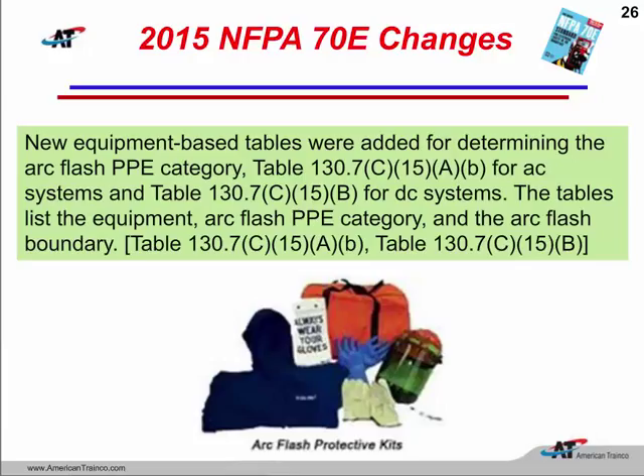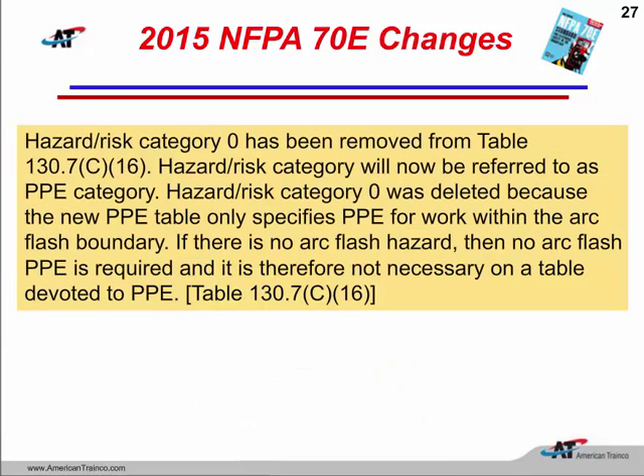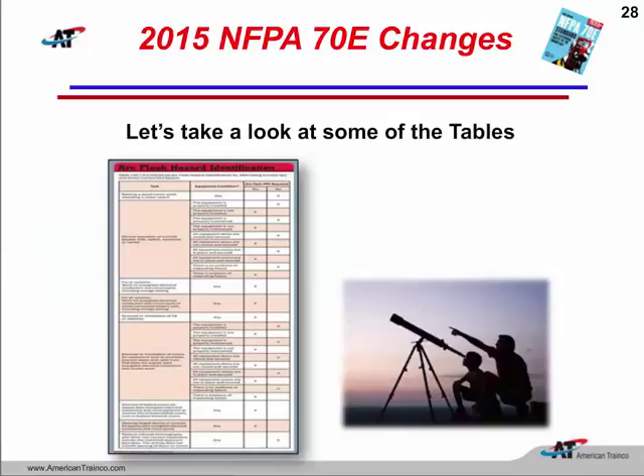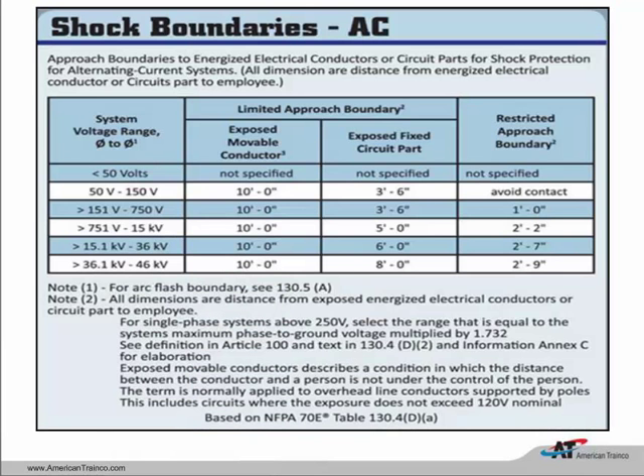So if you walk up to a piece of equipment and you have no label on that equipment whatsoever, these tables are going to be extremely important on how to protect that qualified worker when he approaches that piece of equipment. So they did remove hazard risk Category 0. We have stated that because really there is no arc flash hazard requirement there at all. So let's take a look at these tables a little bit and see how they're going to work with the new 2015. So first, the shock boundaries. So these are AC shock boundaries. You can see we have no prohibited approach boundary there anymore.